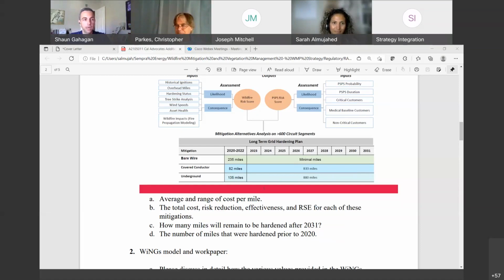Yes, so we looked at our unhardened system historical numbers, and we took all of the faults and turned it into a faults per year per mile number. Then we took the hardened system and came up with the same metric, faults per year per mile of hardened system, and compared the two. For our data, it showed a 47% reduction in the number of faults per year per mile of the hardened versus the unhardened.